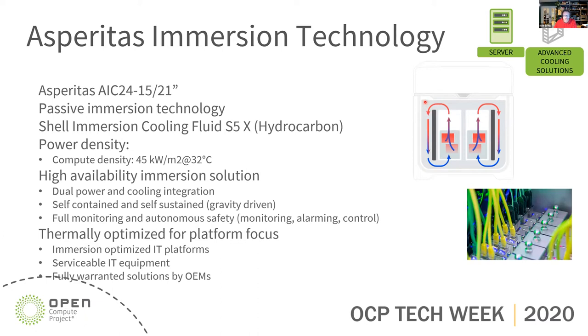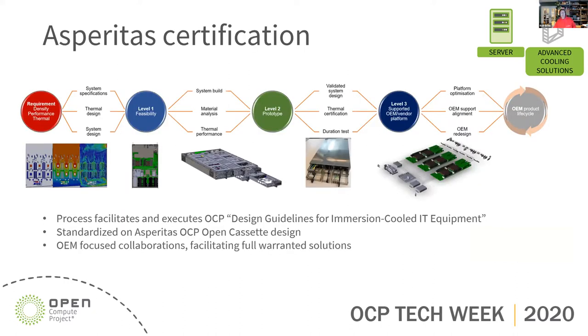The heat exchangers apply a cooling effect which creates higher density and causes the liquid to sink again, creating a nice natural convection circulation mechanism. Because the system is set up symmetrically, it is also symmetrical in nature. Asperitas is heavily focused on optimizing IT equipment for immersion.